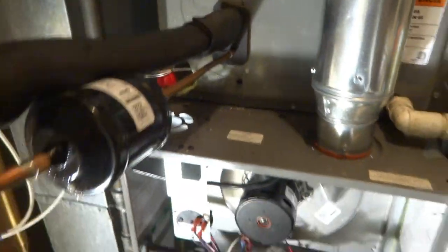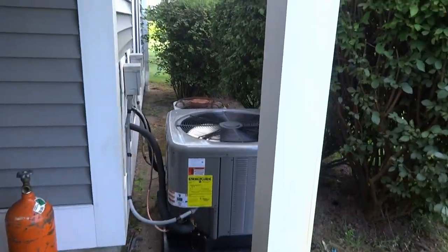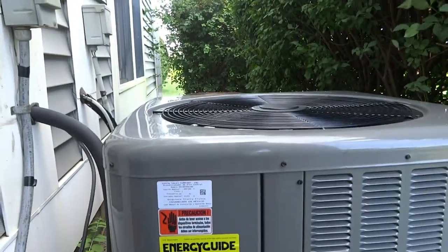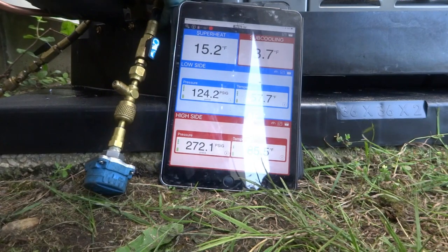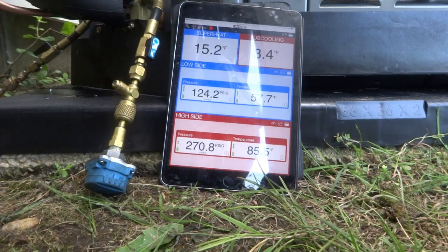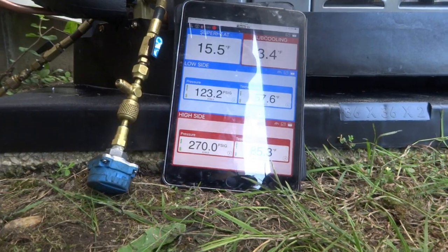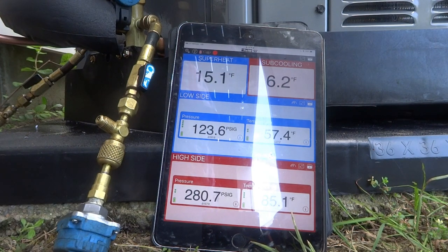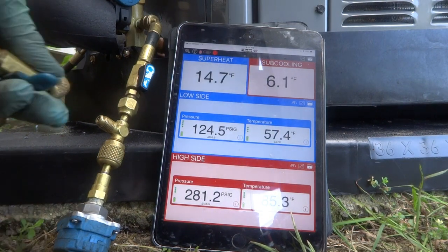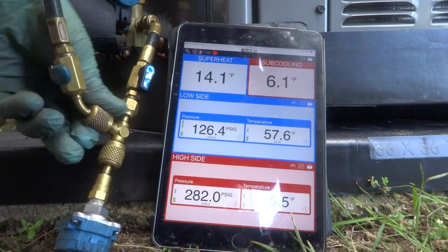Check the cooling. Gauges on it, see what it's doing. See how the subcooling is, we gotta let it run for a bit. But see that at 4, it's too low, we gotta add some gas. It's gonna be around 9, 10, 12, something like that. Give it a little how you doing, mama.